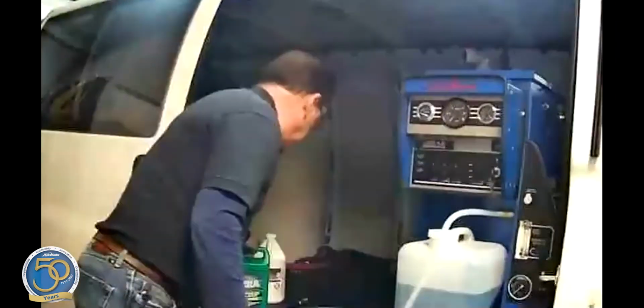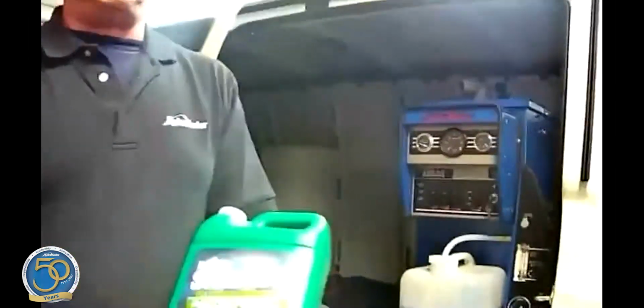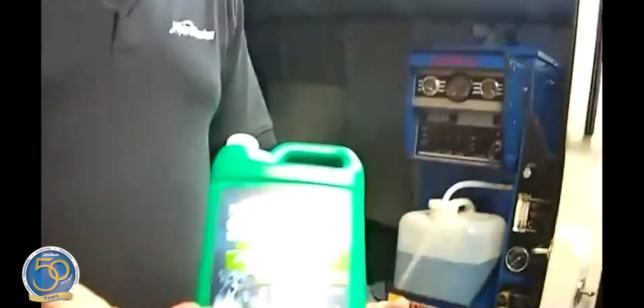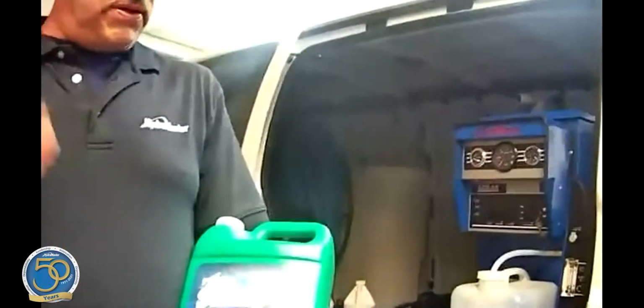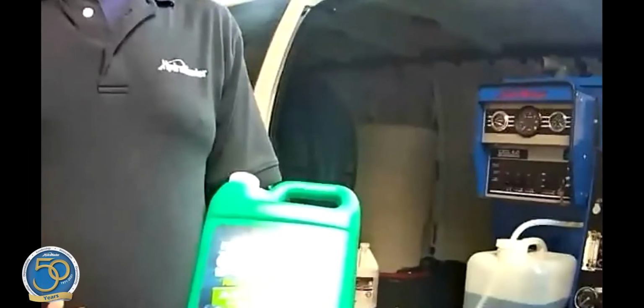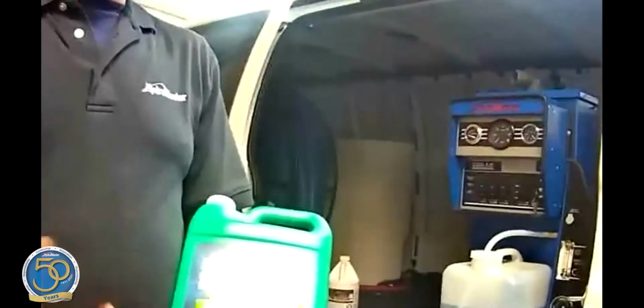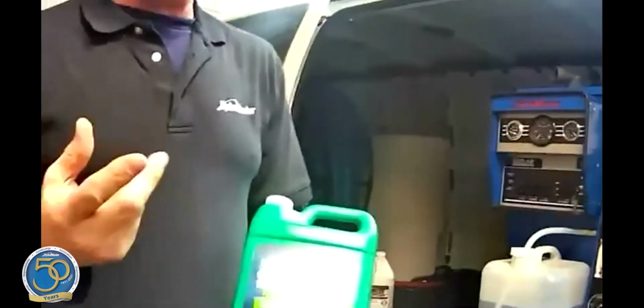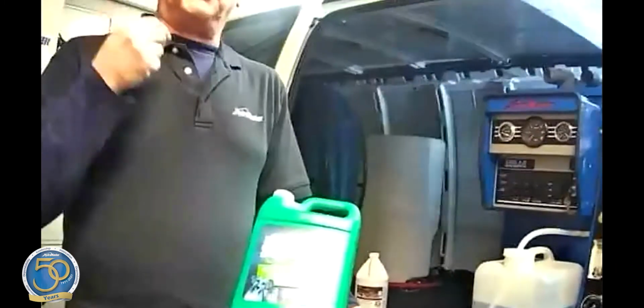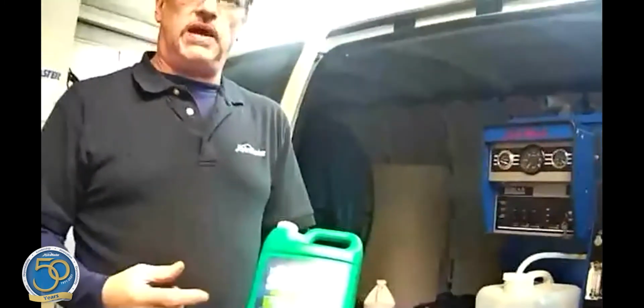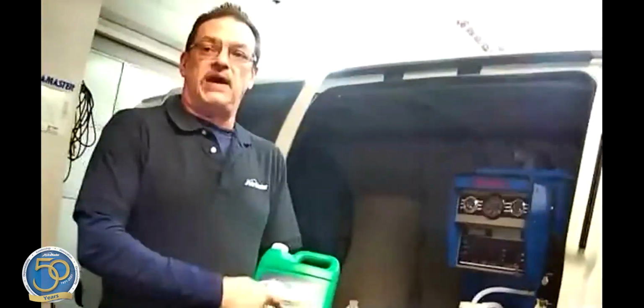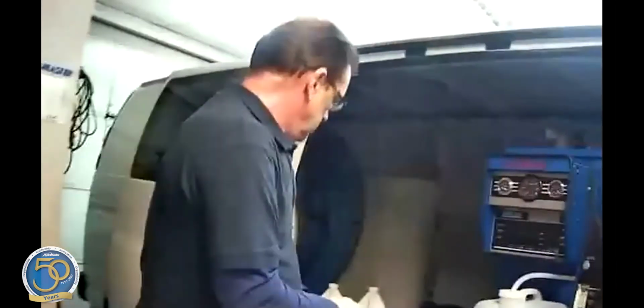In order to prevent that, we always recommend using a concentrated antifreeze. There are other products on the market people have tried, but there's no way of really telling what your dilution ratio is. With this, you can get a hydrometer and actually check the level of freeze protection. Right on the same aisle where you buy the antifreeze, you'll find a hydrometer that tells you what your level of freeze protection is going to be.